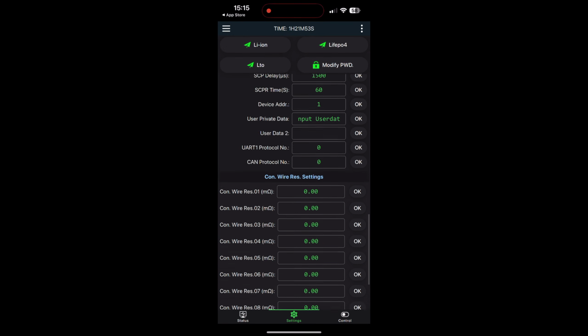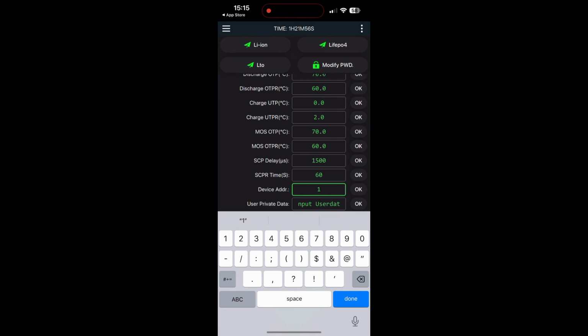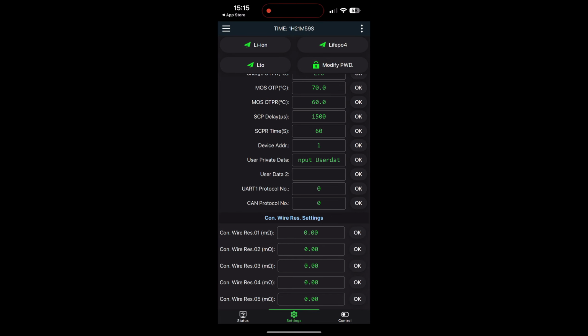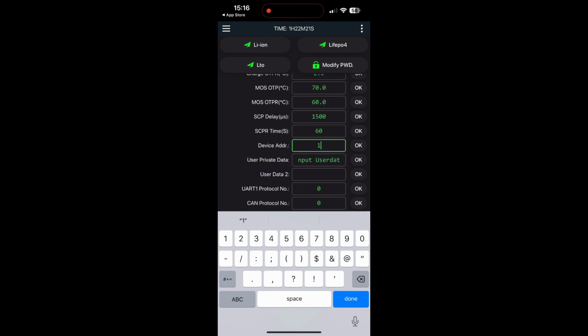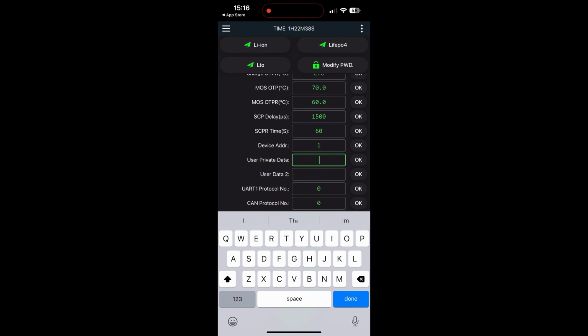These bottom settings, which are further down here, okay, so device address, it's set to 1. All of this information down the bottom is to do with your BMS communicating with other devices like an inverter. So for example, if you've got a BMS that's connected into a communication board and then into an inverter, that's what these settings are for. So basically it's address 1, that's what this BMS would be. Input data, so this is actually talking with the system.